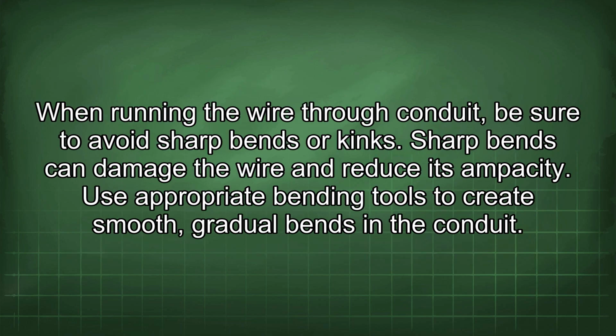When running the wire through conduit, be sure to avoid sharp bends or kinks. Sharp bends can damage the wire and reduce its ampacity. Use appropriate bending tools to create smooth, gradual bends in the conduit.